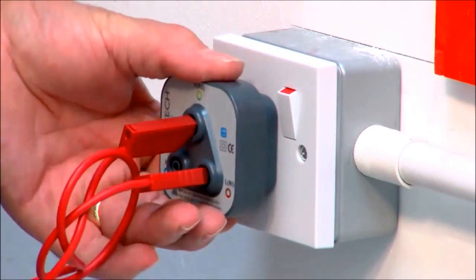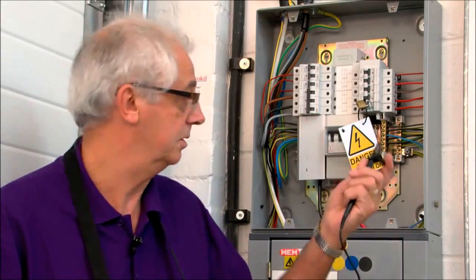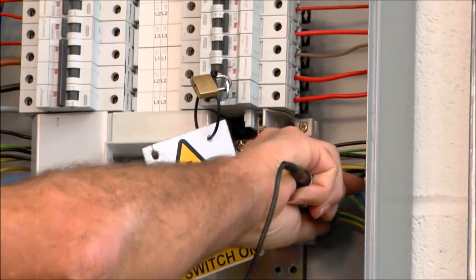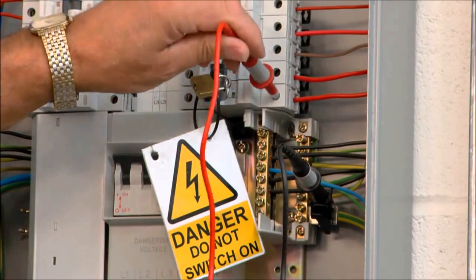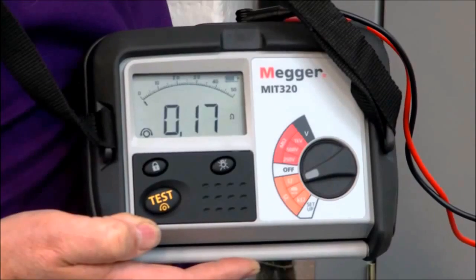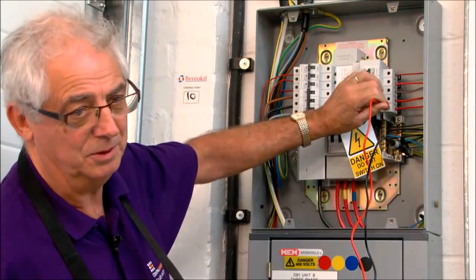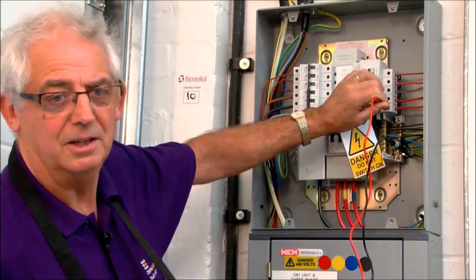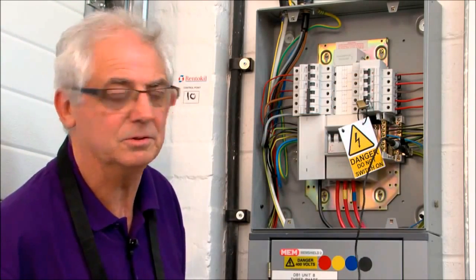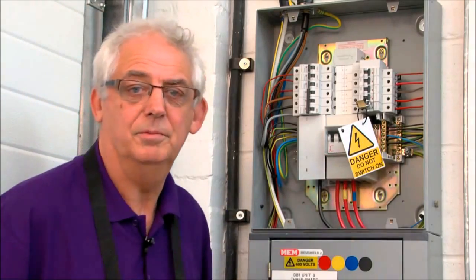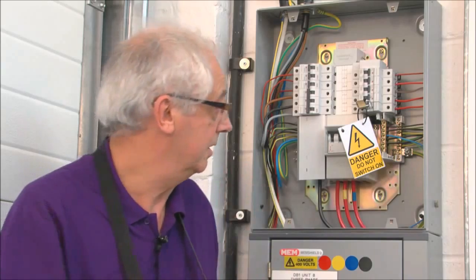I can plug this in, go back to the board, test between line and earth, and that will give me the R1 and R2 reading that I'm after. I've inserted the plug and shorted out the other end of the circuit. I've zeroed the instrument, as you saw earlier, and now all that remains to be done is to carry out the test. But as I said earlier, you must be very careful because there are live conductors around. I've now got a value of 0.2 of an ohm, which is perfectly satisfactory for this circuit, although I'll check it later. I just need to record it on the schedule of test results. Make sure I remove my lead from around by the end of the circuit and replace everything safely.